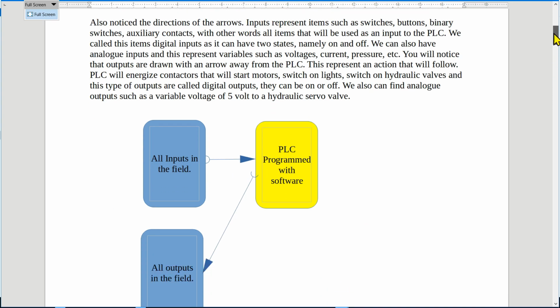Now, also note the direction of the arrows. Inputs represent items such as switches, buttons, binary switches, auxiliary contacts. In other words, all items that can be used as an input to the PLC. We call those items digital inputs, as they can have only two states. Namely, it can be on or it can be off. The signal can be high or low.